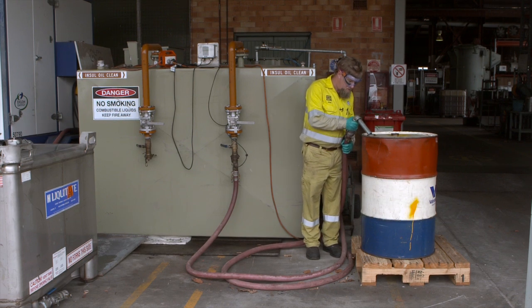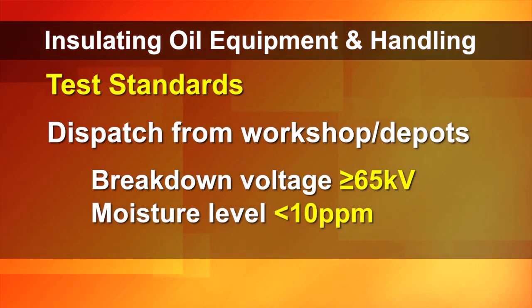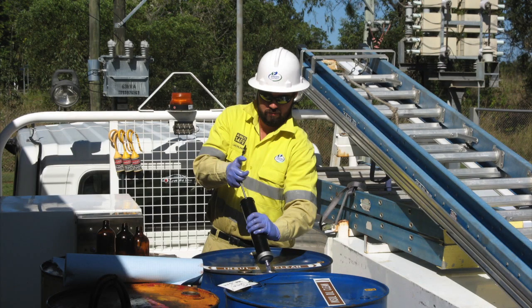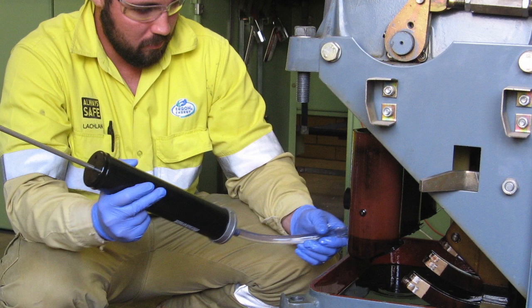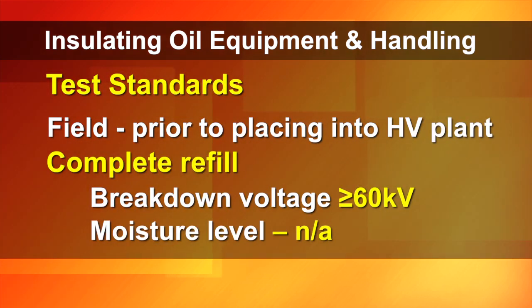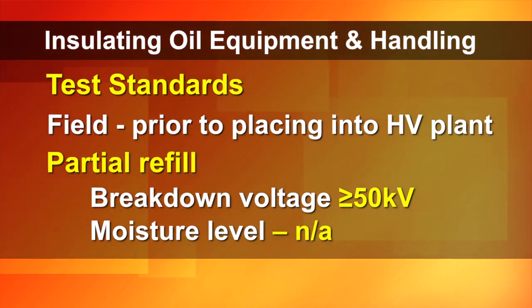Prior to dispatch of the oil out to the substation's crew, the workshop staff are required to get oil to a minimum breakdown voltage of 65 kV with a moisture level of less than 10 parts per million. Out in the field, before the guys place oil into HV plant, generally speaking, if it's for a complete refill, they need to get that oil to a breakdown voltage of 60 kV. There is no requirement for moisture testing in the field. Slight variation on that: if you're only doing a partial refill, you need only to get that oil to a 50 kV breakdown level.